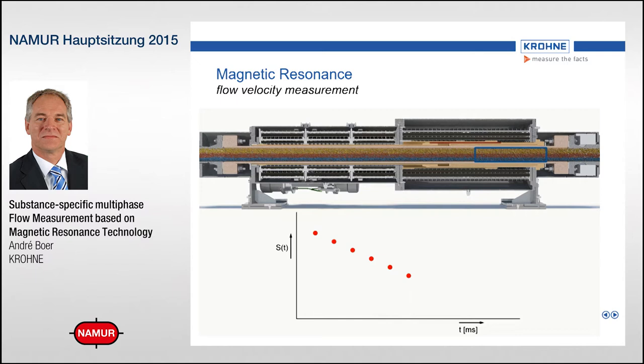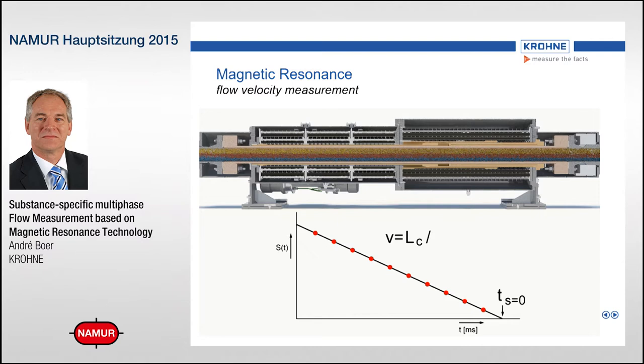By means of these RF signals, we can detect and learn more about where those protons were attached to. We can tag certain protons in the measurement section by sending out a special RF pulse first. Every subsequent RF pulse, we are interrogating the number of tagged protons still inside the measurement section. Less and less tagged protons remain because of the flow — in other words, the amplitude decreases over time, and this decreasing amplitude tells us the flow velocity of these tagged hydrogen protons.